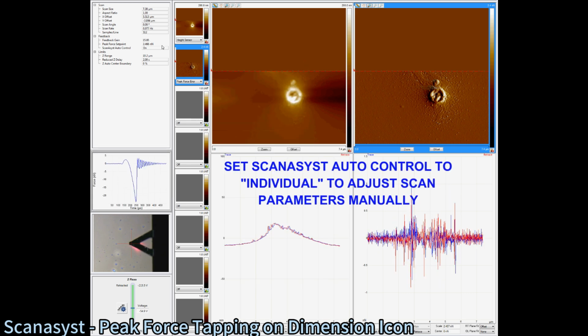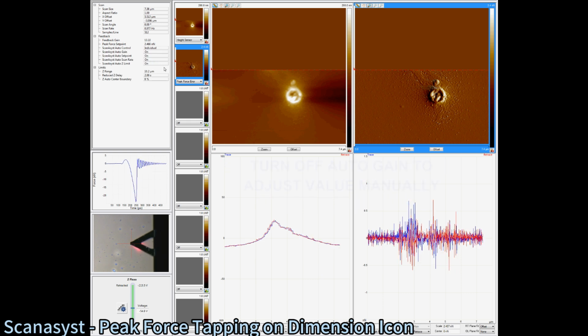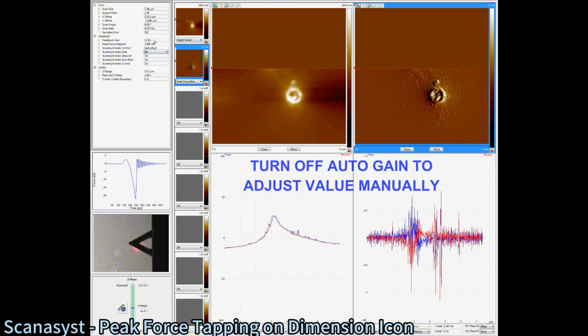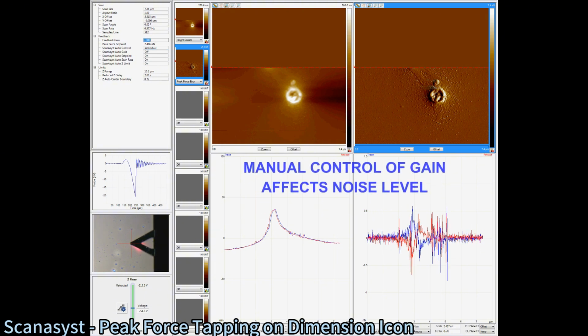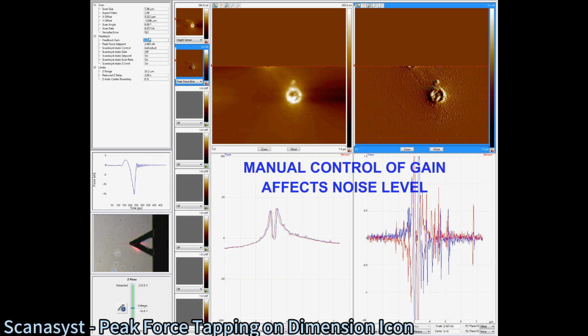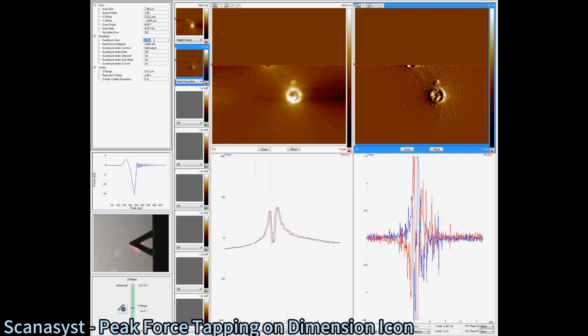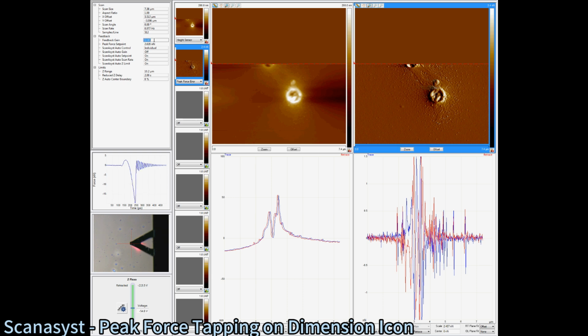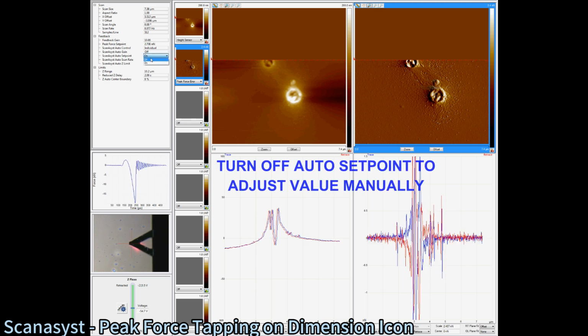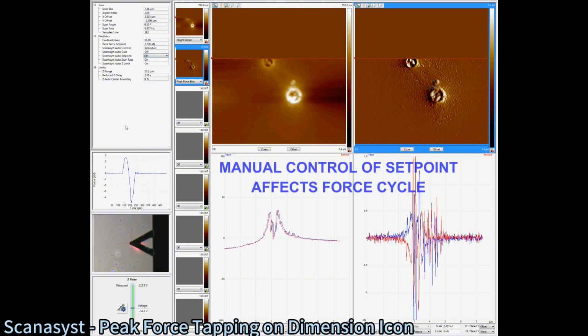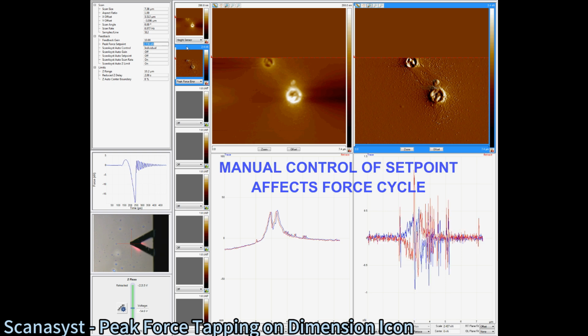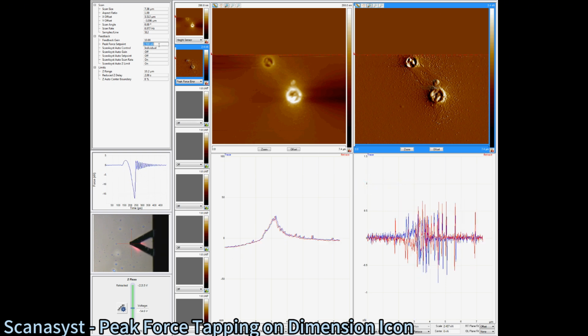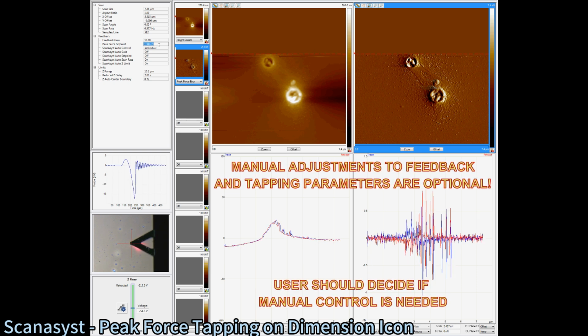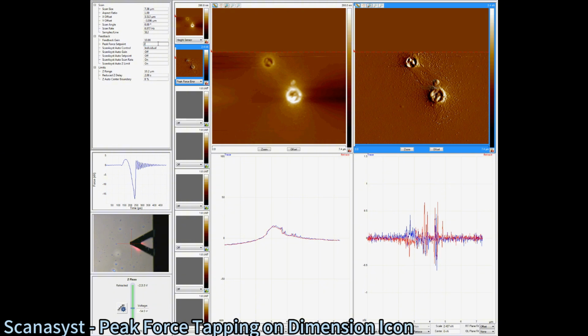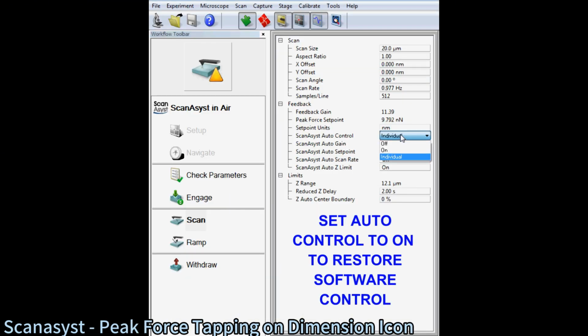The user has the option of turning the ScanAsyst Auto Control off and selecting individual control over parameters such as set point or gain. Adjusting the gain value can affect the noise level of the image. Adjusting the set point can increase or decrease the force load cycle on the sample. Manual tuning of the individual scan controls is entirely optional and may improve the image quality, but if adjustments are providing no significant improvement, then it may be preferable to leave the auto control on and let the software adjust the values while the probe is scanning.